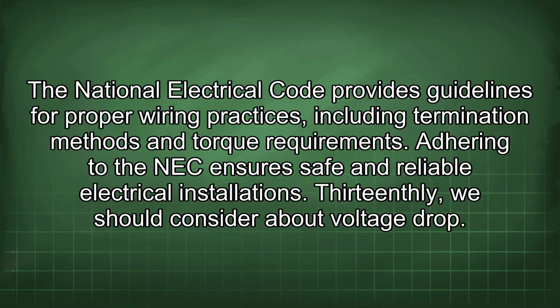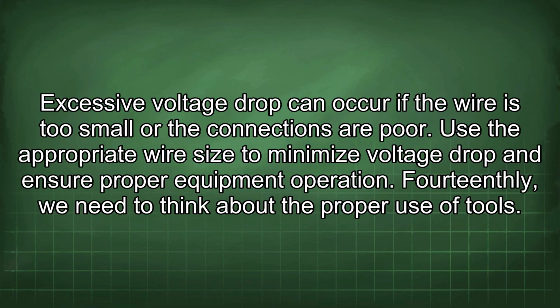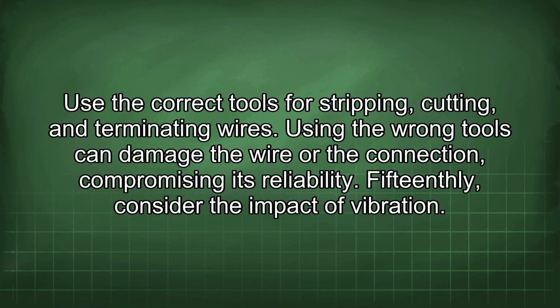13thly, we should consider voltage drop. Excessive voltage drop can occur if the wire is too small or the connections are poor. Use the appropriate wire size to minimize voltage drop and ensure proper equipment operation. 14thly, we need to think about the proper use of tools. Use the correct tools for stripping, cutting, and terminating wires. Using the wrong tools can damage the wire or the connection, compromising its reliability.